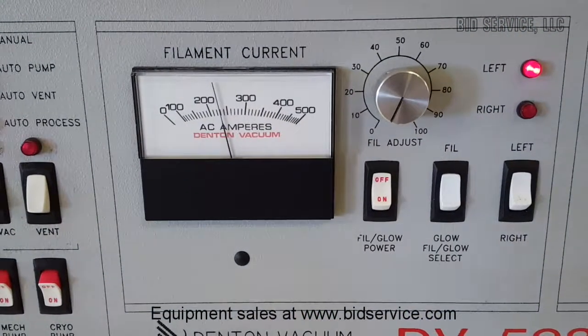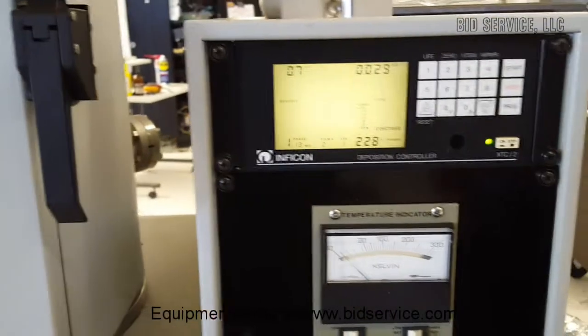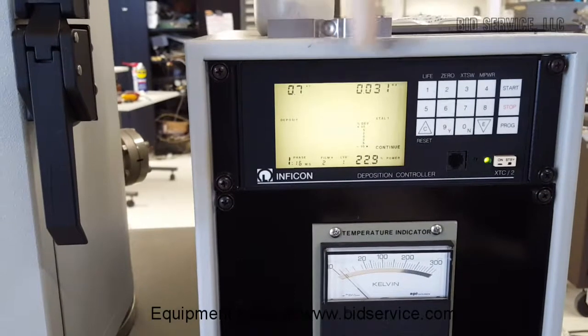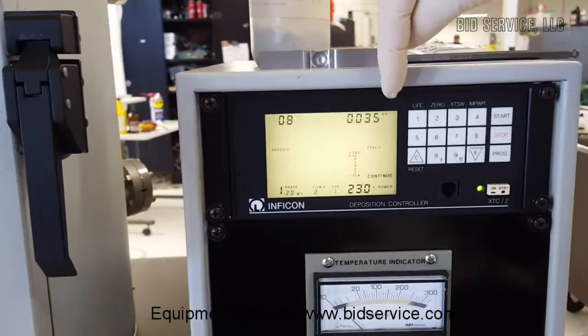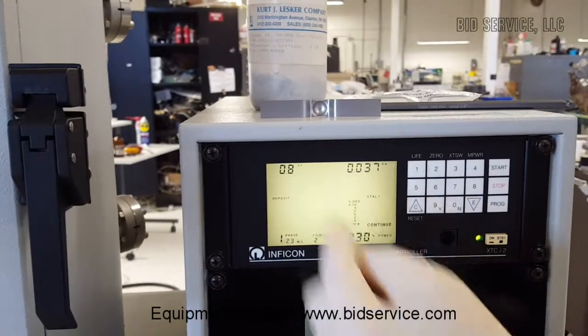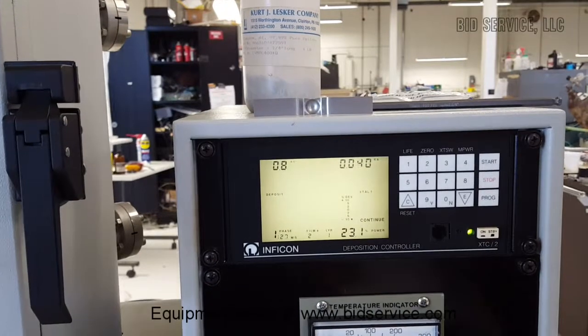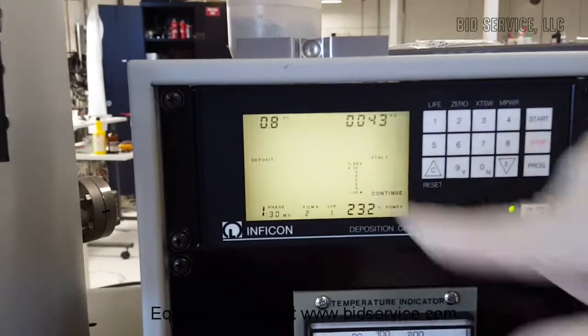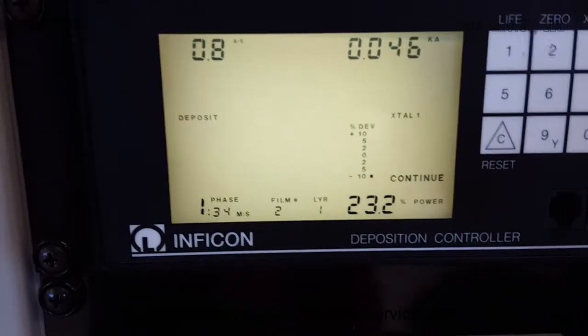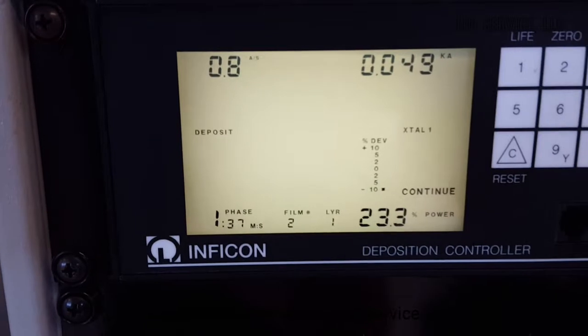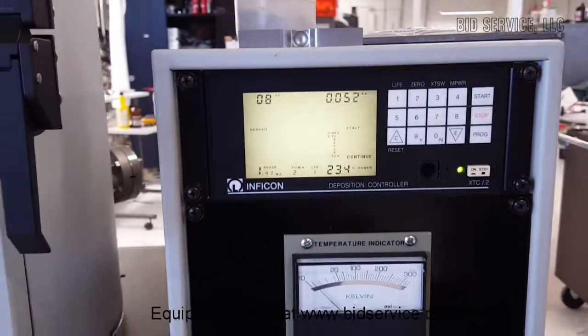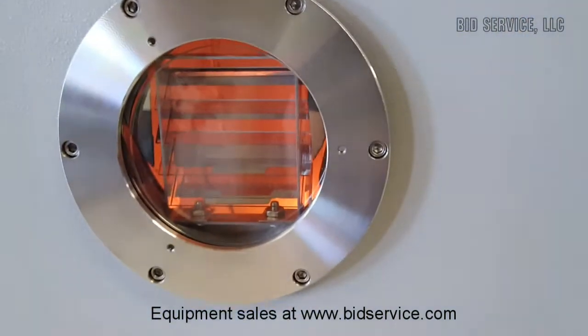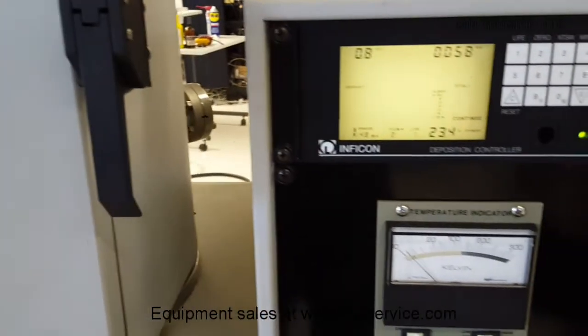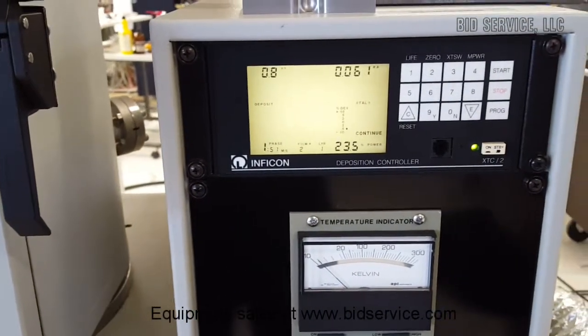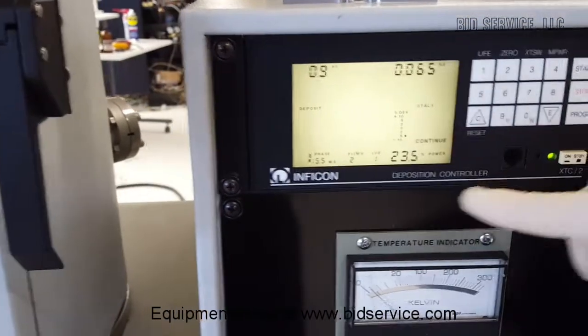Quick look at the filament current. We're up around 230 now. So as the power is increasing, we're getting a little bit more deposition rate. The total is adding up, and again, we're looking to hit 0.500 at a rate of 1.0. Here's the deviation that's showing you how far off you are from the actual deposition rate that's programmed in. See that start moving around 0 once it gets to 1.0. If you look inside, you can see the brightness of the filament. Alright, at 1 angstrom per second, it's getting pretty close now, and we're at 23.5.